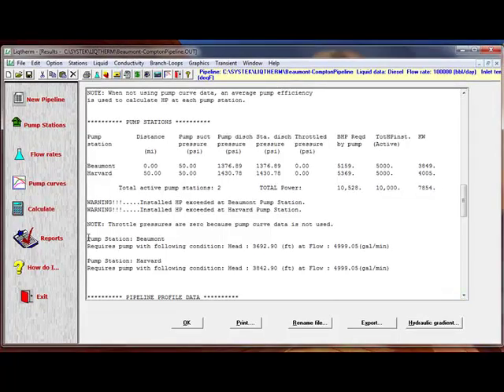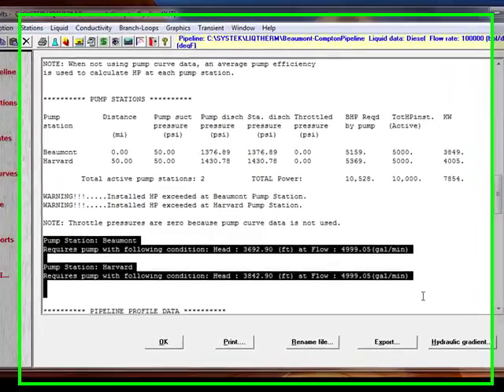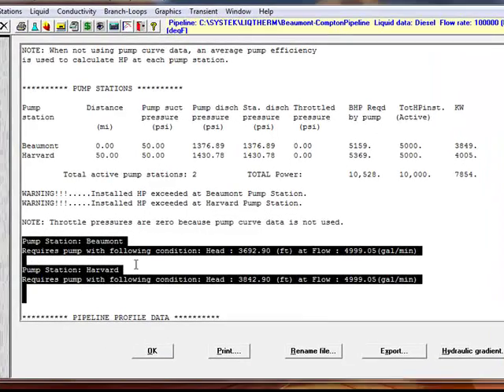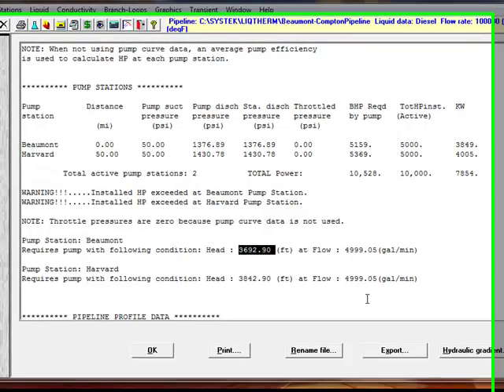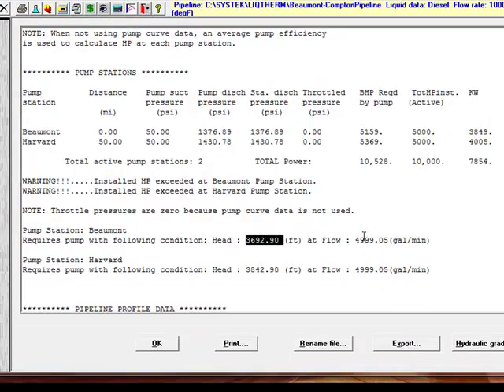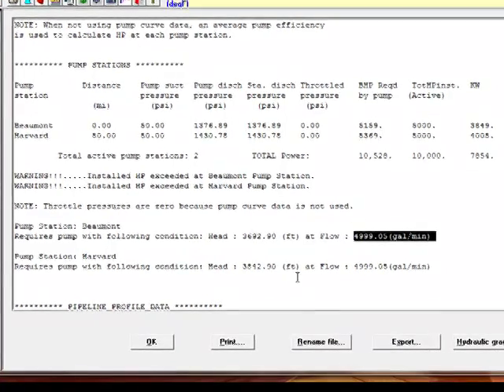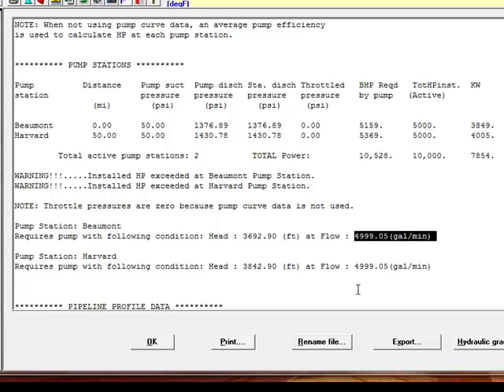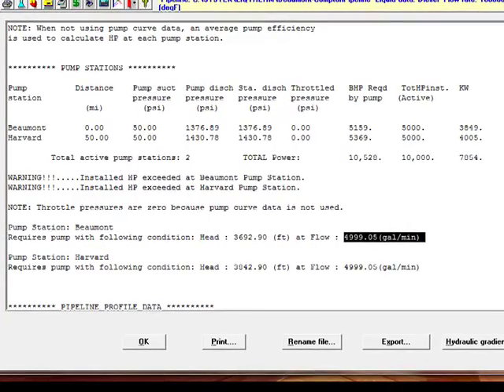The pumps required are specified here. At Beaumont, you need a pump with a head of 3,692.9 feet at a flow rate of 4,999 gallons per minute, and the Harvard pump station requires a pump with 3,842.9 feet at the same flow rate of 4,999 gallons per minute.